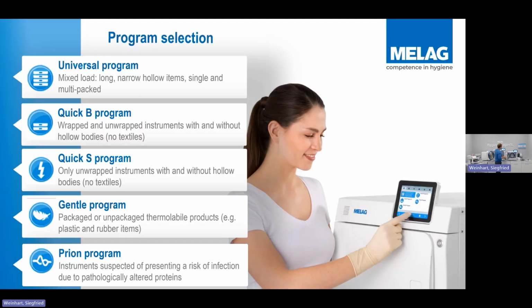It's important that your sterilizer has a really good selection of programs, and those programs will match the load types, because there is not one size fits all when it comes to a sterilizer. But what we try to look at is giving you programs that maximize your working day. So you'll have universal load, okay? And the universal program, even though it might say hollow, narrow hollow, universal in a vacuum autoclave is a vacuum cycle. And that's where this question comes up. Well, can I do mixed loads in there? That universal cycle is a full load. And that was where you could have a full load, mixed load of wrapped and hollow, wrapped and unwrapped, or you could put a full load of wrapped on there as well.